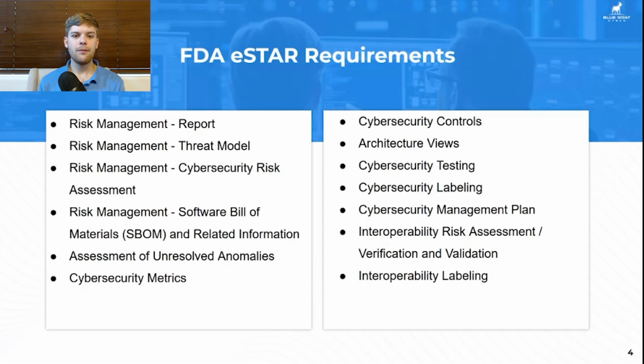The next thing is we want to see a software bill of materials and then some related information around it. The software bill of materials is essentially a log of everything in the device. It talks about all the third-party components, any of the code written by the manufacturer, and then how it all ties together. It's meant to be a comprehensive list of what goes into the device. The reason for that is if one of those components is insecure and has a vulnerability, that vulnerability may make its way into the system and pose a risk.